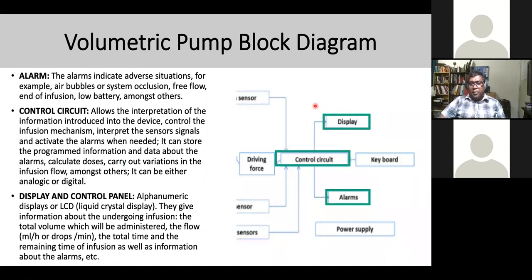So this is a part of the display and control circuit and alarm. When you talk about alarm, everyone knows all medical devices have alarms that indicate issues. For volumetric pumps, you're going to see alarms that indicate air bubble, occlusion, free flow, end of infusion, low battery, and other indications as well.